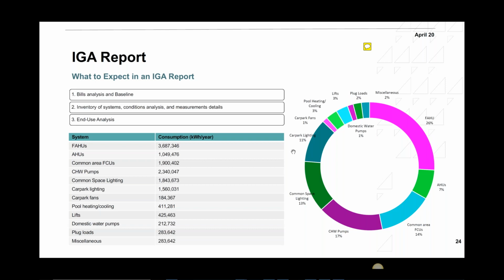This particular building's data is mainly the common area consumption, so it doesn't include the apartments, and it's on district cooling, which is why we don't see the chillers like mentioned before. So looking at the FAHUs, air handling units, and common area FCUs would be good, along with chilled water pumps which also have higher consumption. I'd look at outdoor air handling units first, then chilled water pumps, then lighting, then common area FCUs—that's more than 80% of the consumption. Domestic water pumps don't consume much energy, so don't waste time there.